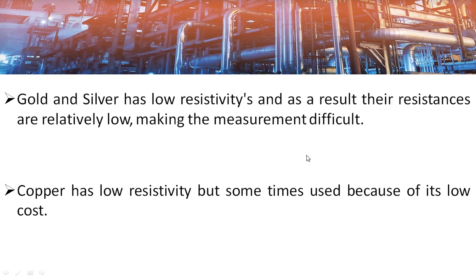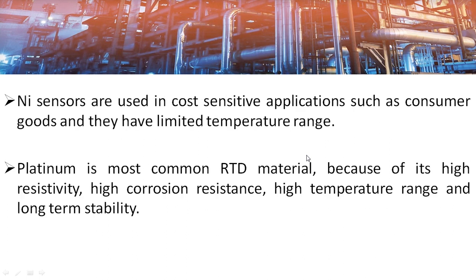Copper is also having low resistivity but it is used in some applications like measurement of motor winding temperature because of its low cost. Nickel RTD sensors are used in cost-sensitive applications like consumer appliances and heating and ventilation systems, and they have a limited temperature range.